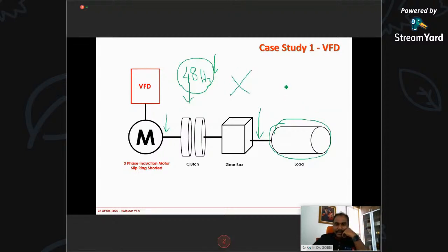There is no saving at all, because eventually after about 1 month, the company complained and they brought this back to 50 hertz. That means now this particular system is running with a VFD at 50 hertz as normal. That means you have to maintain the VFD, you have to pay additional cost for the air conditioning system, and additional maintenance cost, with zero savings. This is a bad example of where you should not be using the VFD. So not all motor systems should be connected to a VFD.